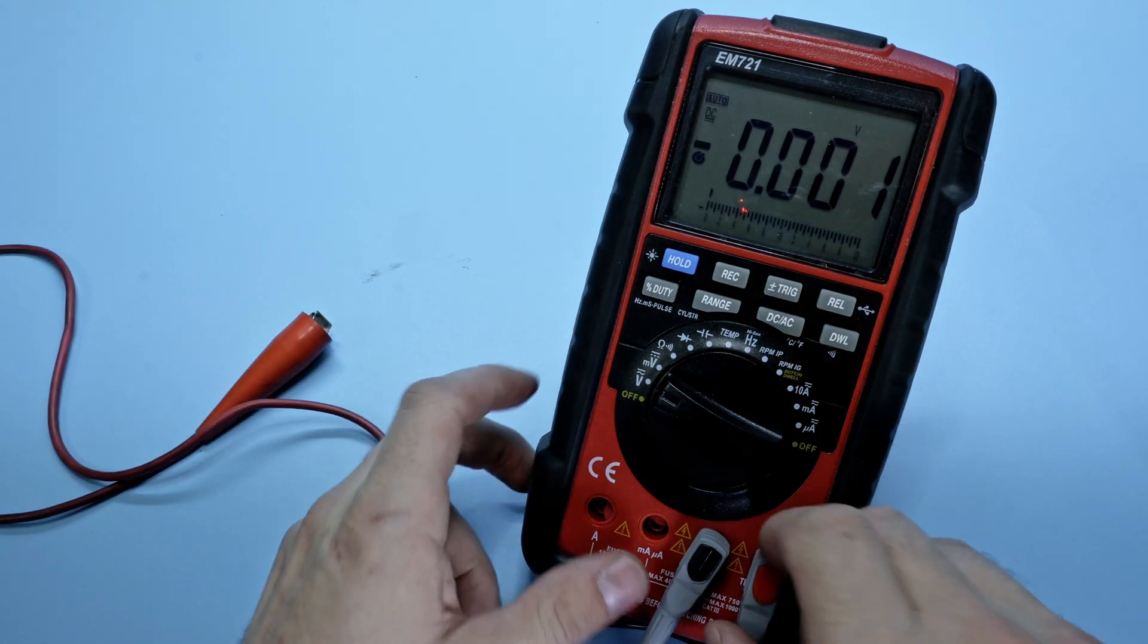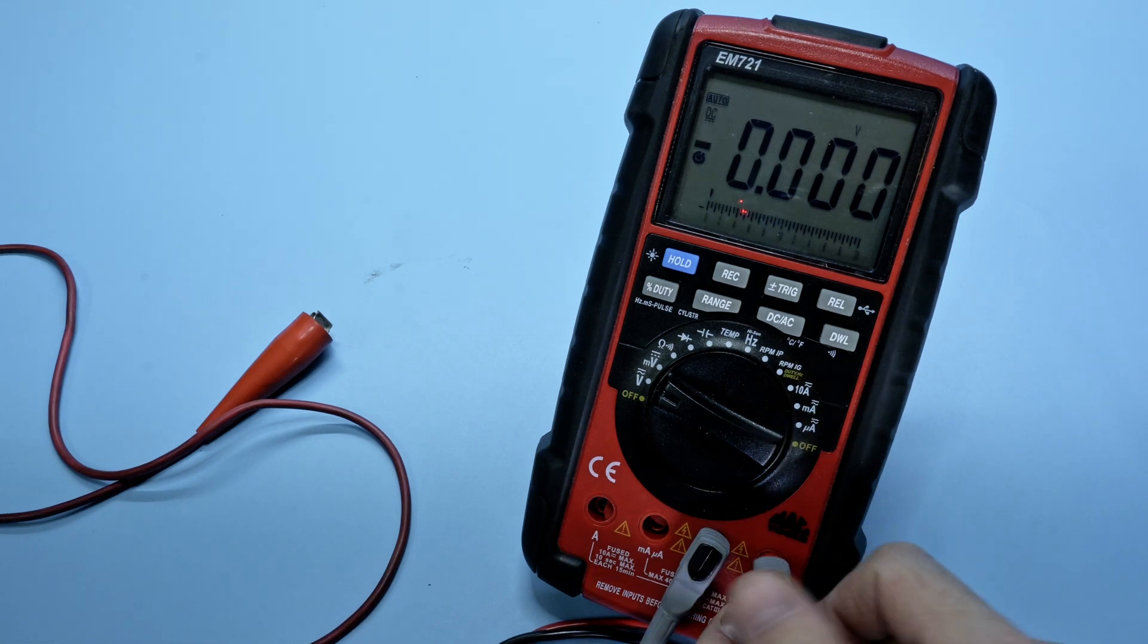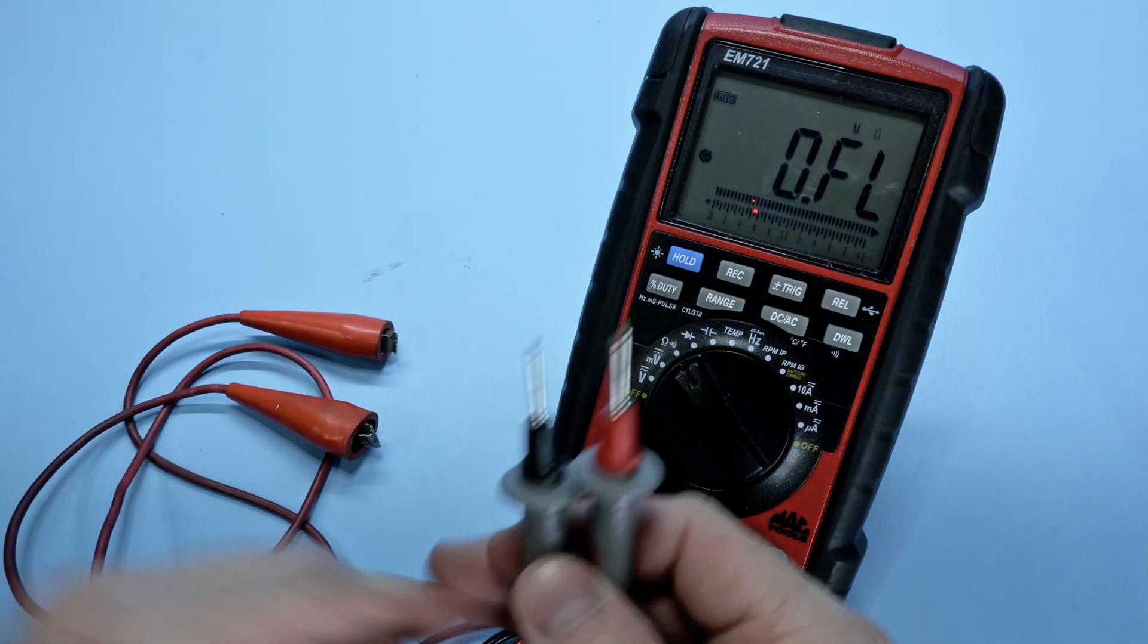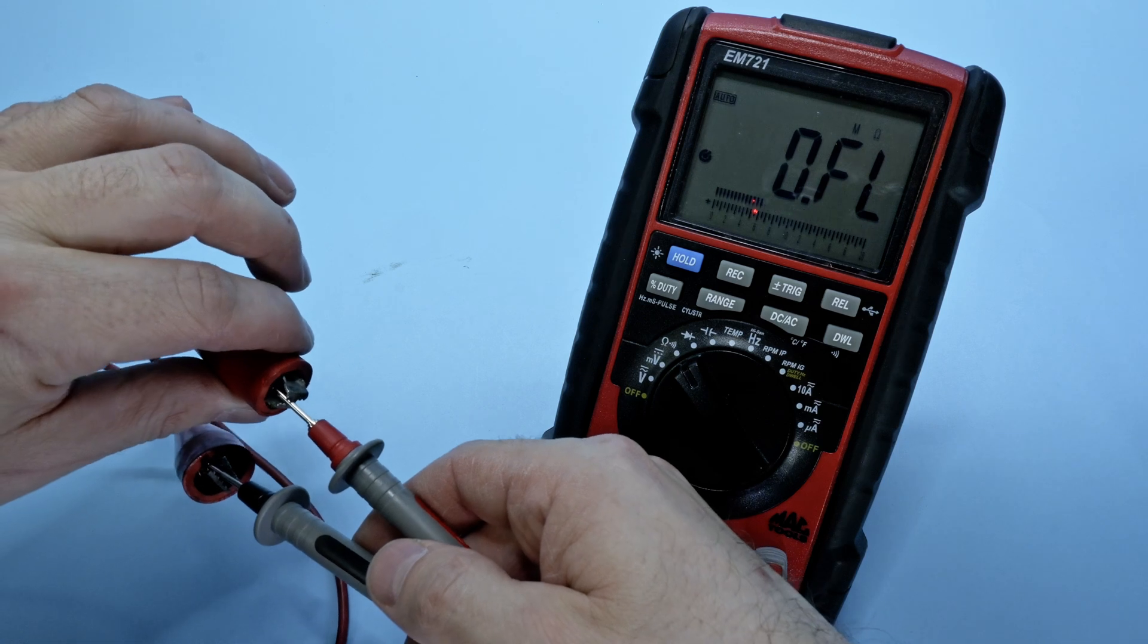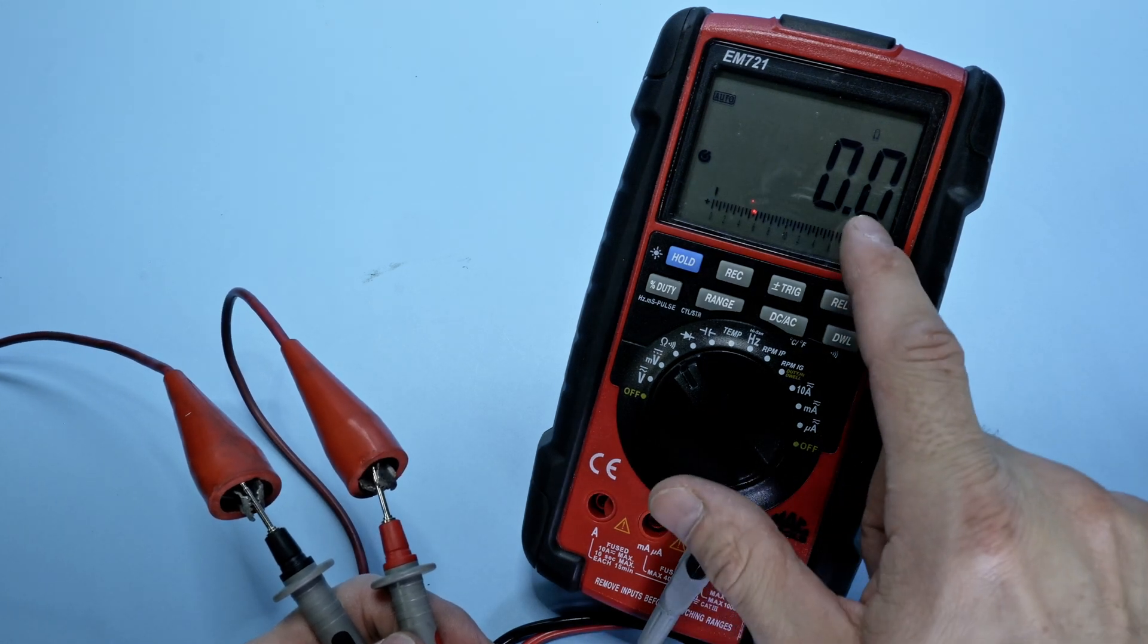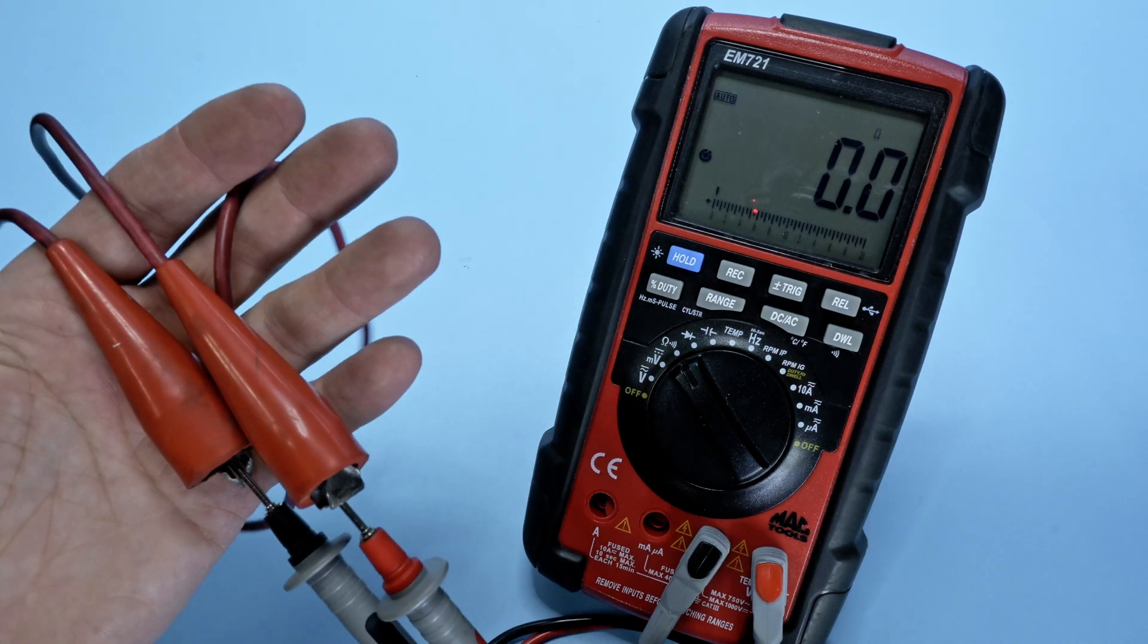To read resistance, we leave our red lead connected in the same port that we used for voltage. And then we simply move our selector knob to the resistance setting. Now, if I wanted to check the resistance of this piece of wire right here, I would simply take my two leads, connect them to my wire, and I should have a very low reading. 0.1 of an ohm. That's not too bad. If I had a higher reading, such as 5, 6, 7, 8 ohms or higher, then I know that there is a fault in this wire, and this is a faulty wire.